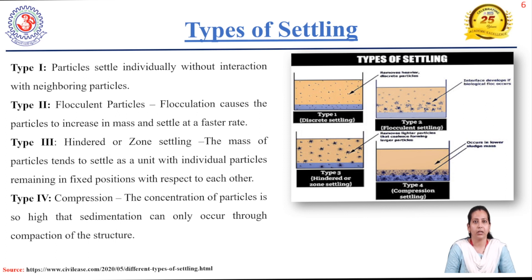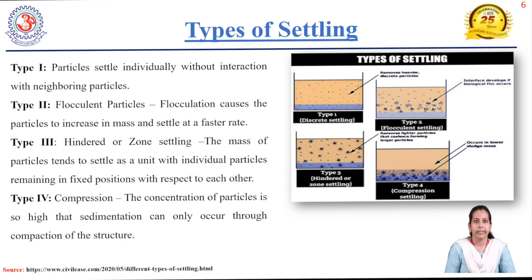Type three is hindered or zone settling, where flocs are formed and the mass of particles tends to settle as a unit, with individual particles remaining in fixed positions relative to each other. Type four is compression settling, where the concentration of particles is so high that sedimentation occurs through compaction of the structure. These are the four types of settling carried out in the settling tank.